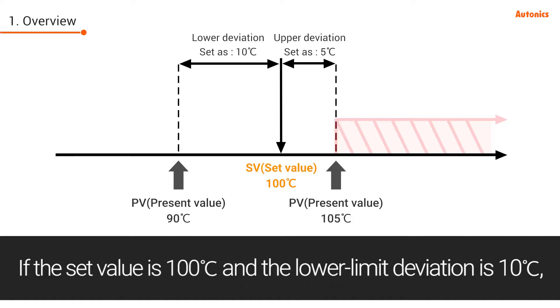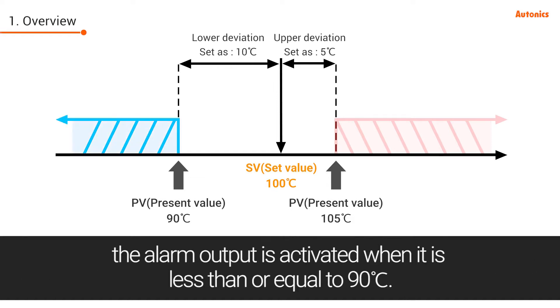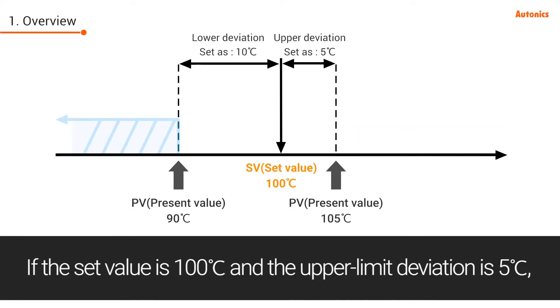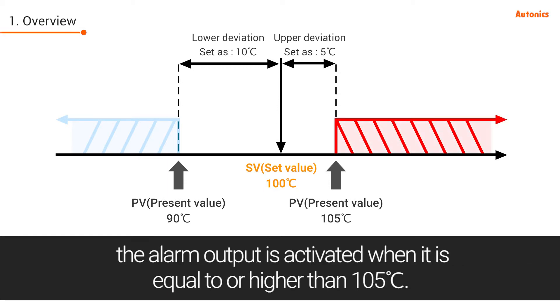If the set value is 100 degrees and the lower limit deviation is 10 degrees, the alarm output is activated when it is less than or equal to 90 degrees. If the set value is 100 degrees and the upper limit deviation is 5 degrees, the alarm output is activated when it is equal to or higher than 105 degrees.